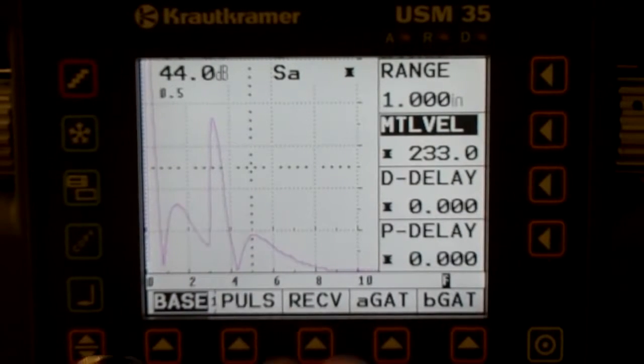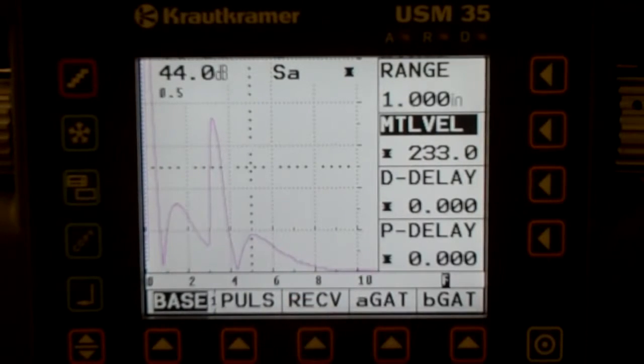All this right here, all this jargon, this is the near field. So we're starting at 0, and we actually have a near field that stretches out to about 0.8 inches in steel. So if we slap our transducer on here - you can't see that I'm putting the transducer on there, so let me move you.